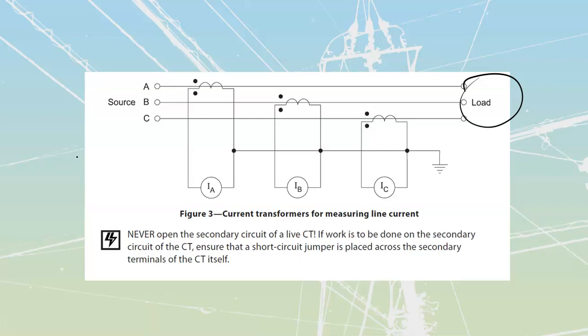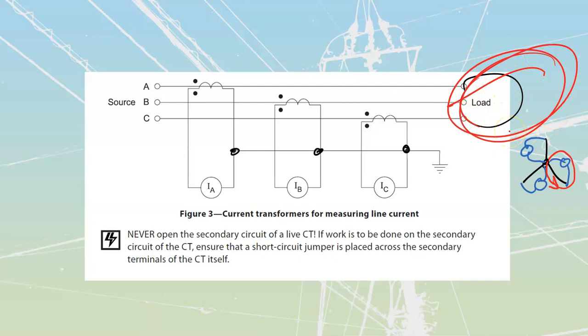Looking at my connection here, I see it's once again going to be a Y type of connection. Each of these CTs connects across, with a central line, and my ammeter itself is connected across like that. We'll have an ammeter there, another ammeter here, and another ammeter going across here, just measuring the amount of circulating current going through that winding based on whatever the load is drawing through the system.